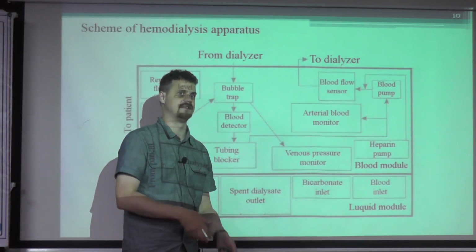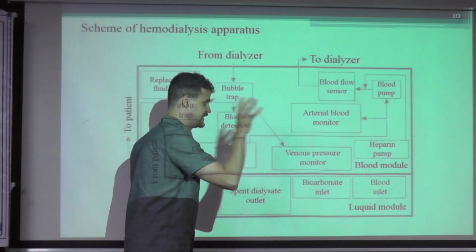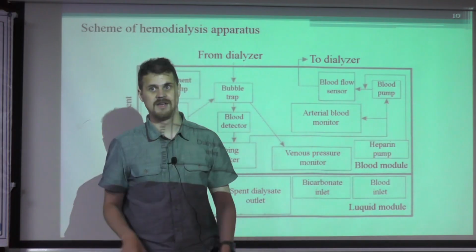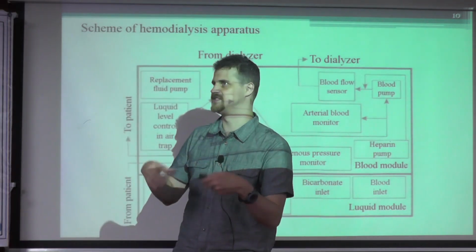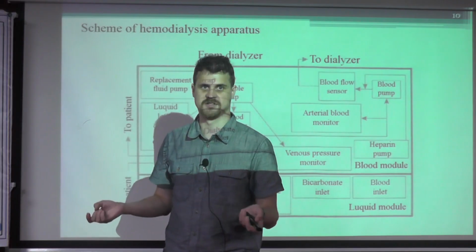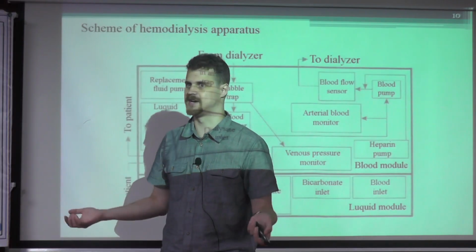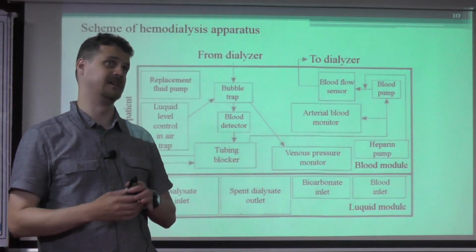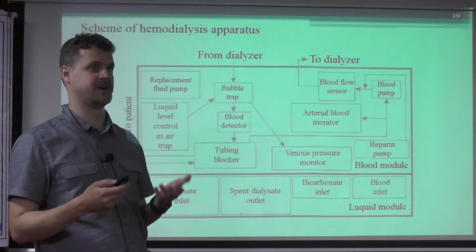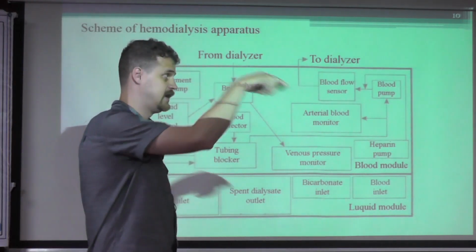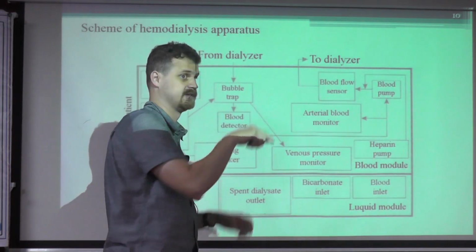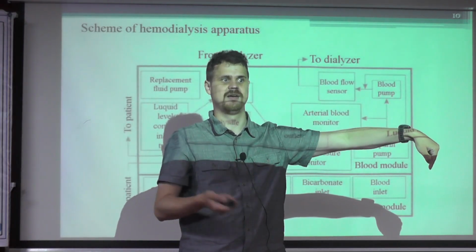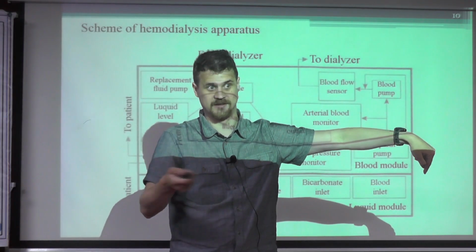At the same time, there should be the detectors of blood presence in a dialysis solution, because we need to make sure that the membrane of the mass exchange unit is not permeable, not just for proteins, but for blood cells as well. There can be a condition when there is some poorly manufactured mass exchange unit, or at some point of the hemodialysis we exceeded the transmembrane pressure that led to the malfunction of membrane. And that means that the blood will go from the perfusion part of the dialysis to the dialysis itself. That means that patient will start losing blood in that case.